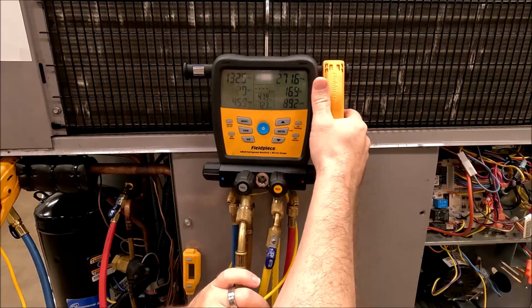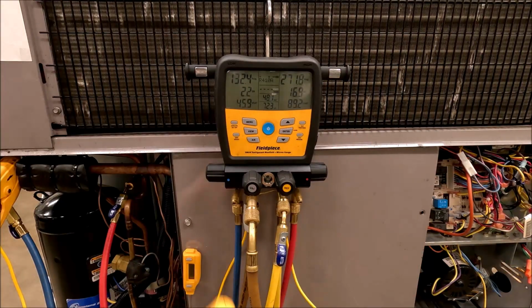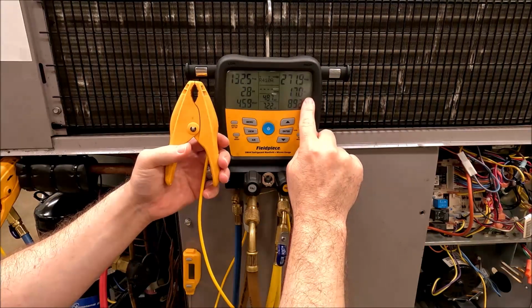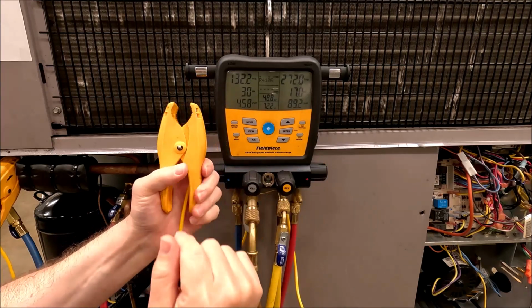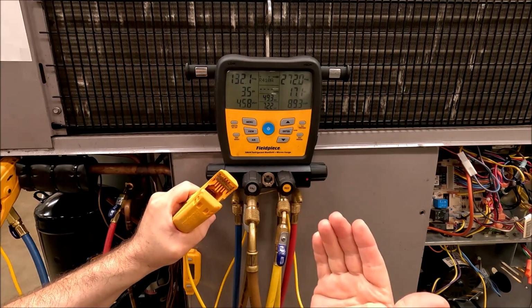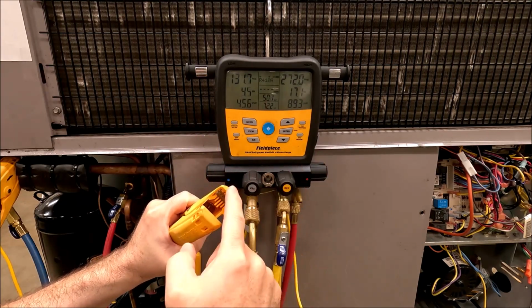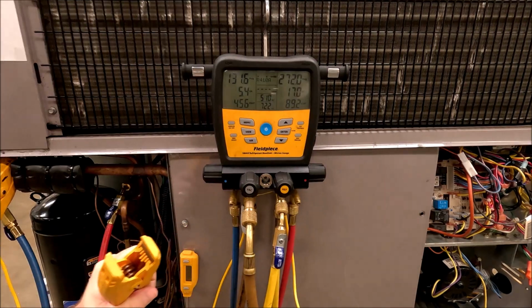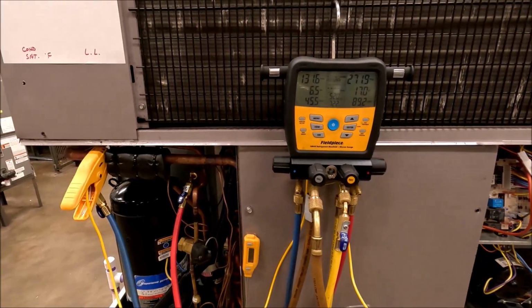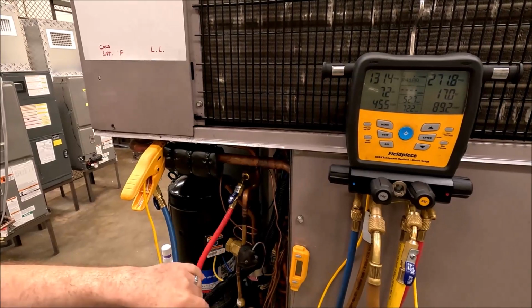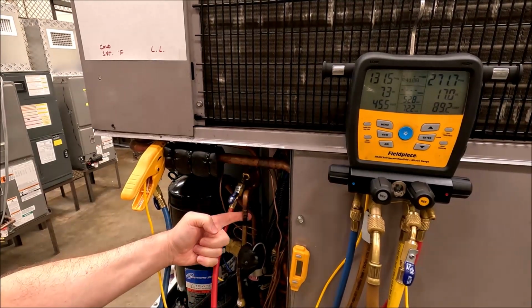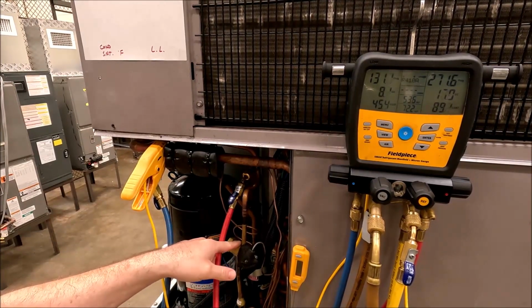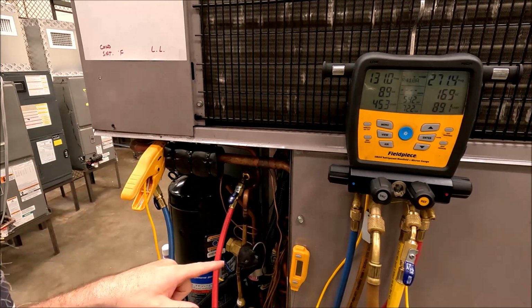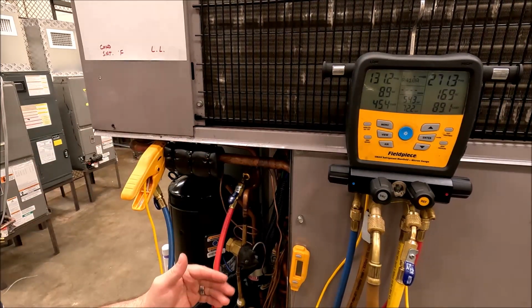Got to make sure you keep it straight. So I'm going to take this one, and even though it's already reading superheat, it's because of the air temperature. You can't stop it from reading the temperature. You have to put it on the proper place. So we're going to go right down here, and just like before, there's that liquid line. I've identified my metering device. I know that's where the pressure goes from high to low. So find the hot side.